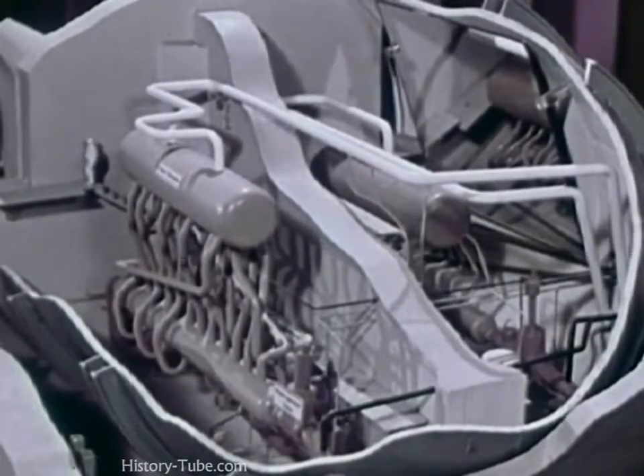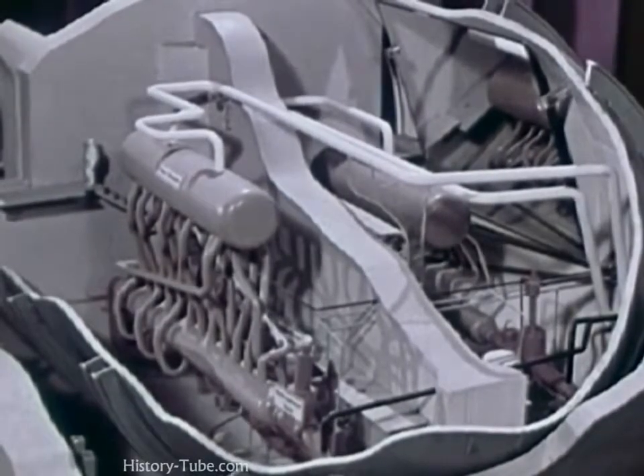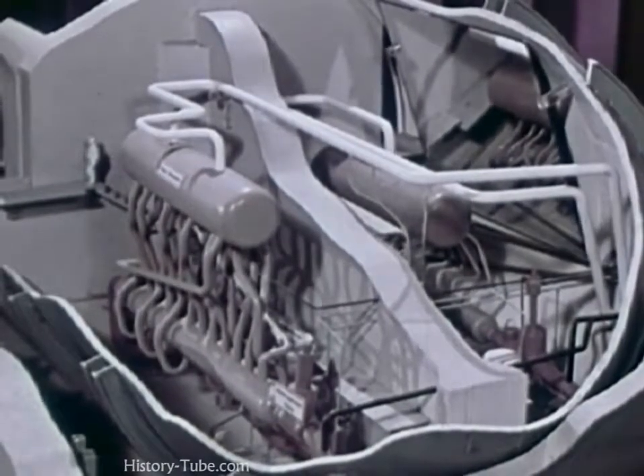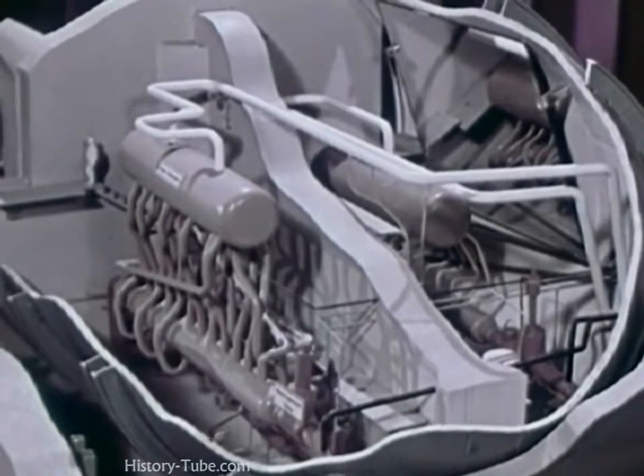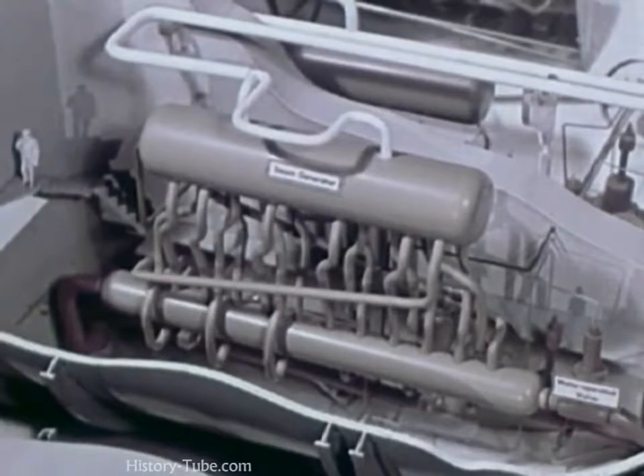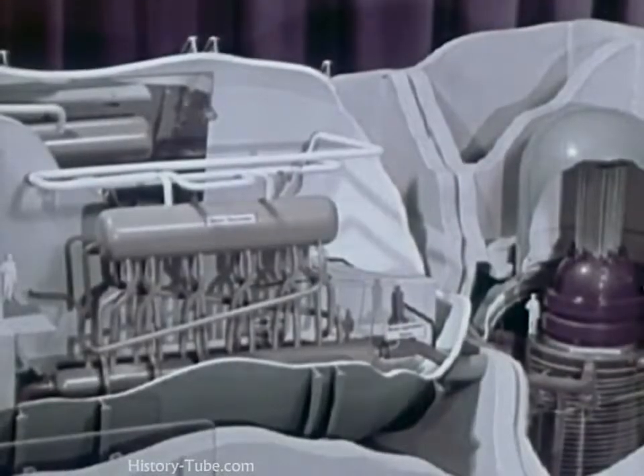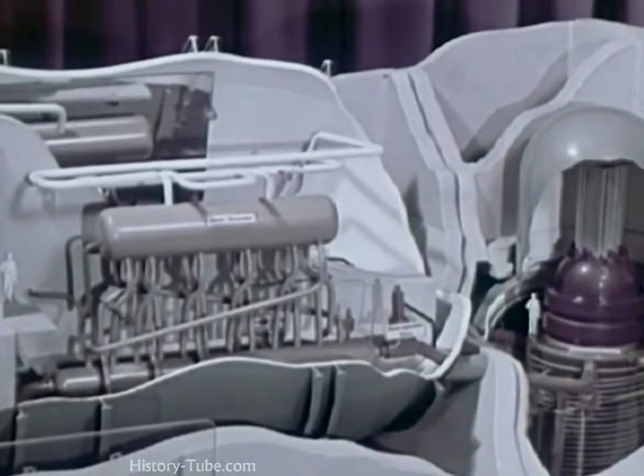This is one of the 2 similar boiler chambers. A concrete shield separates the 2 loops within it, permitting access to an inactive loop while the plant is operating. The steam generator consists of this steam separator and heat exchanger. The 4 loops are capable of producing a total of over 1 million pounds of steam per hour.